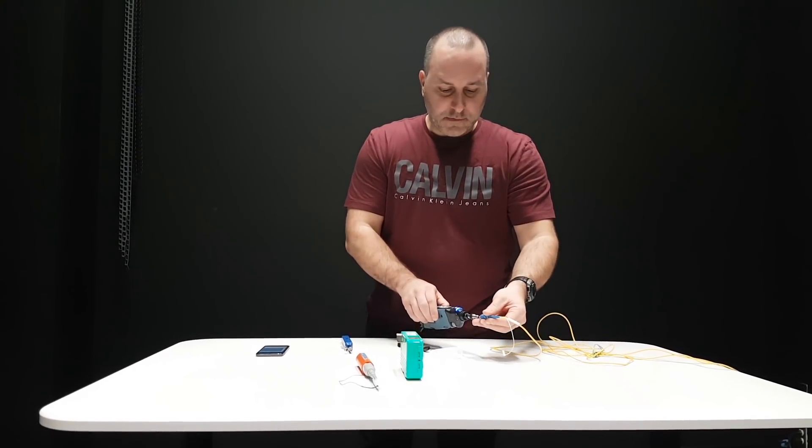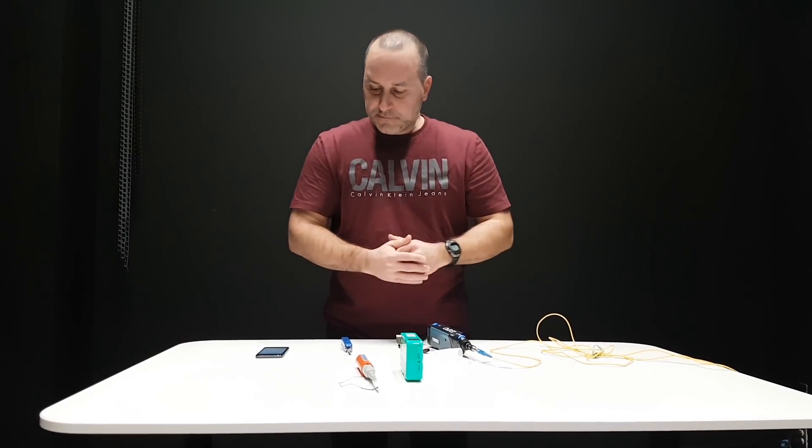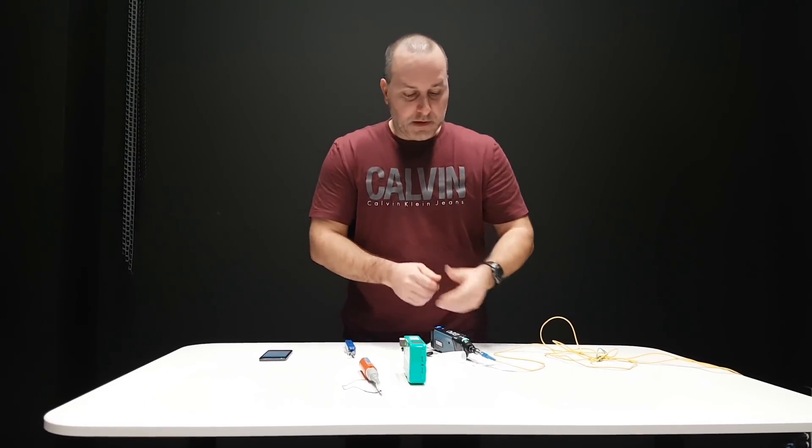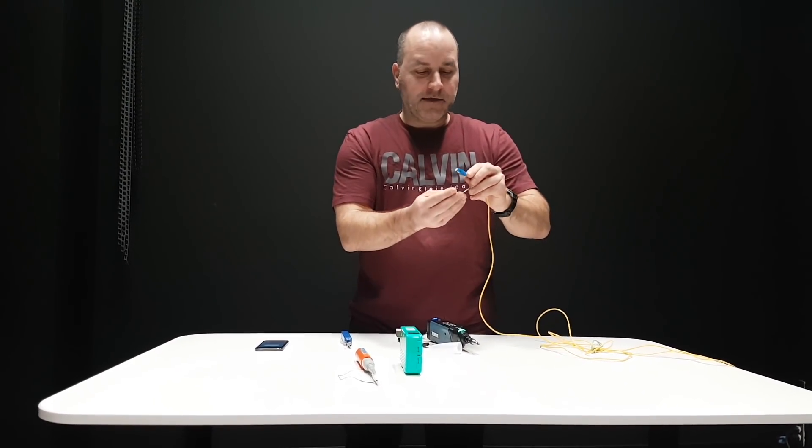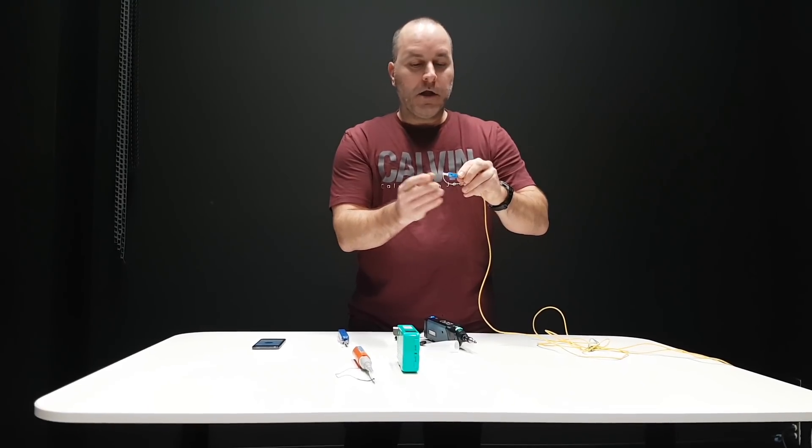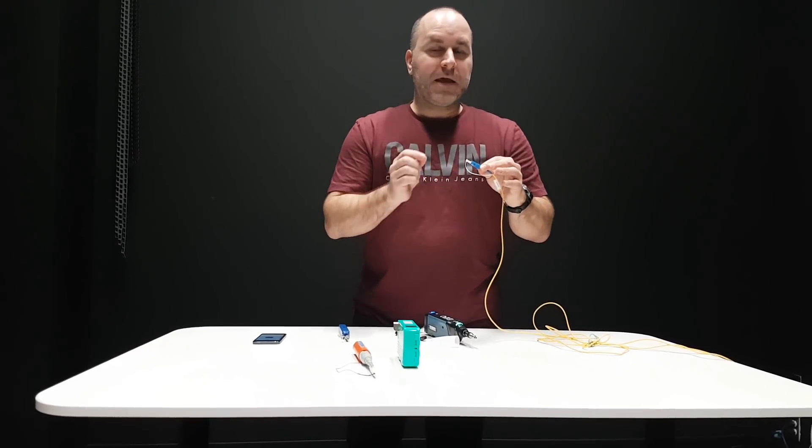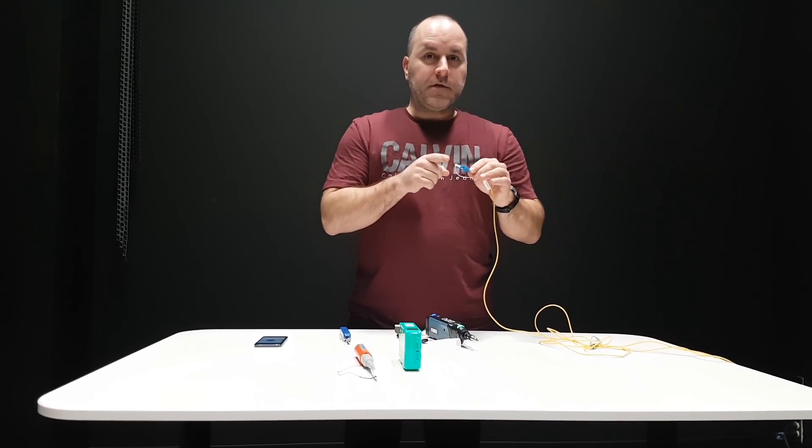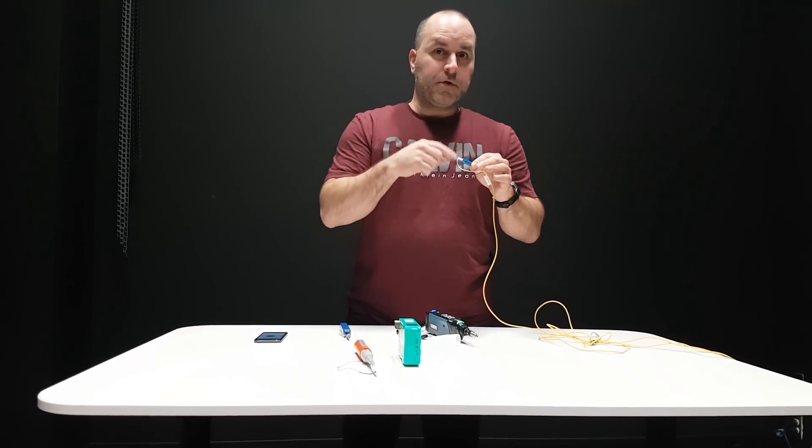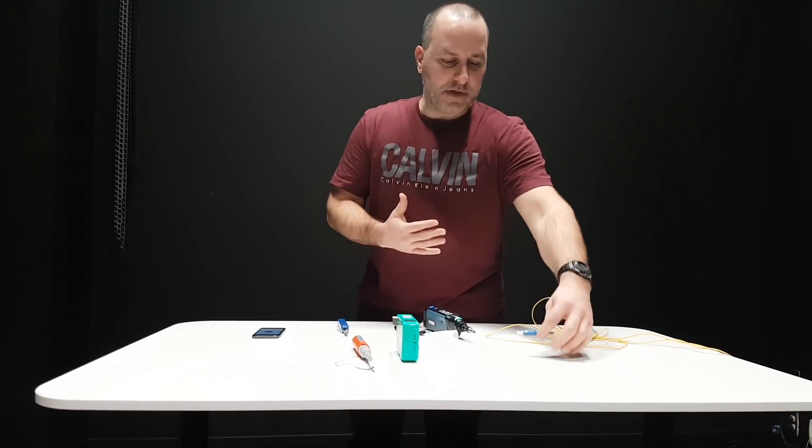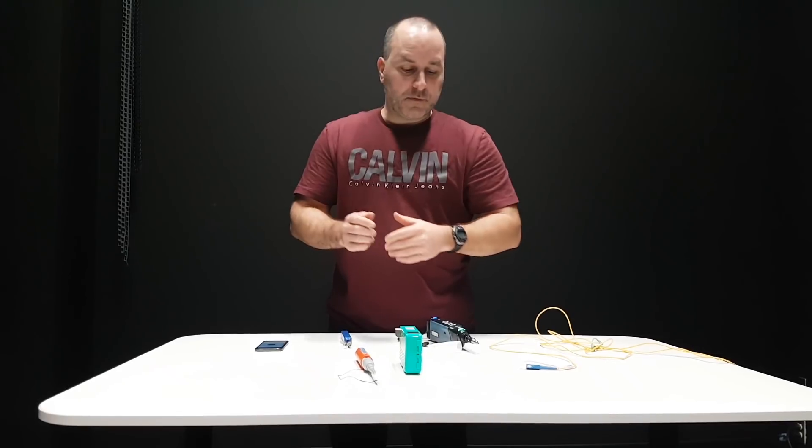Once you test it with the probe, and the analysis runs its course, and then you get a passing grade, then if you're not ready to connect it yet, you can simply put the dust cap on it. Don't push it far to the end, don't push it completely in, because there is some dust in the caps, and if you push it to the end, then it's possible that you will put some dust back on to the connector end, and you don't want to do that. So you just put the cap back on, and then when you're ready to plug it in, you just plug it in.